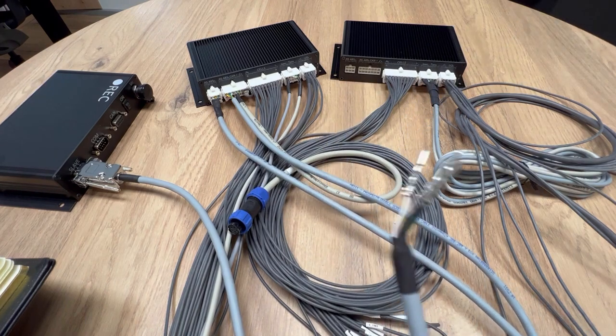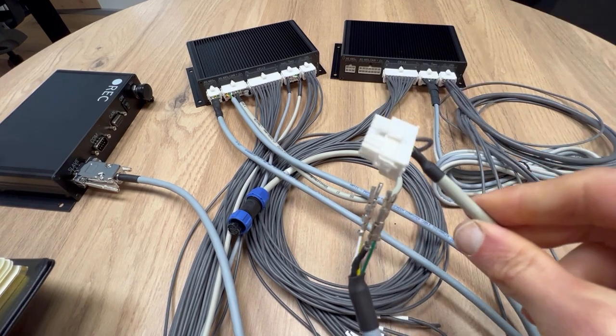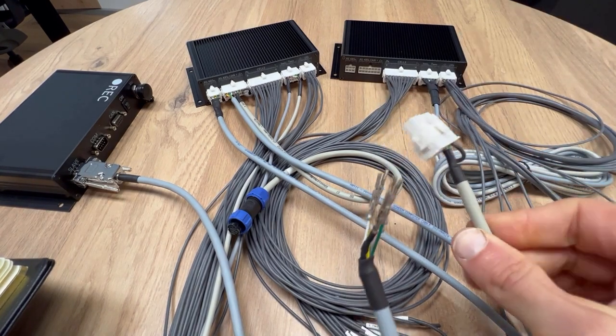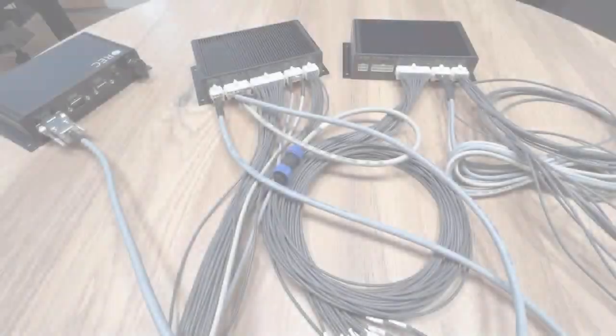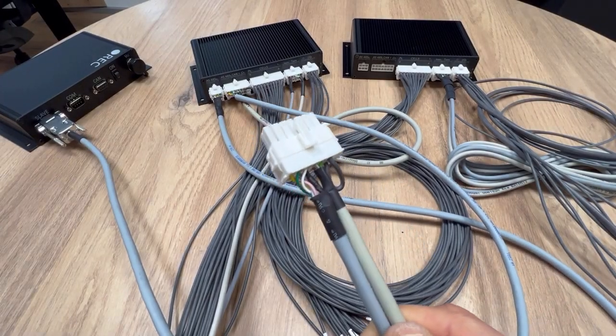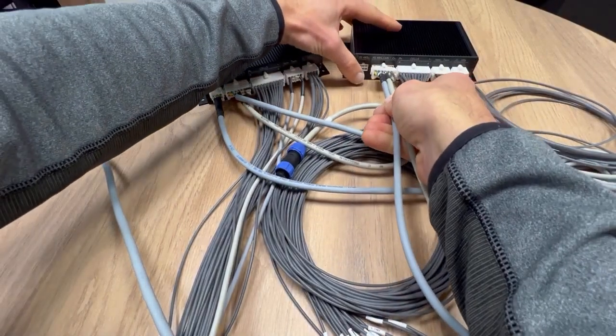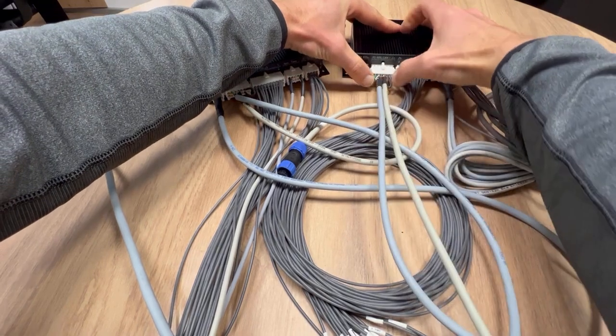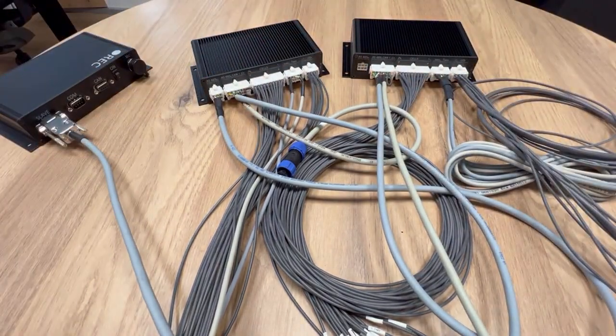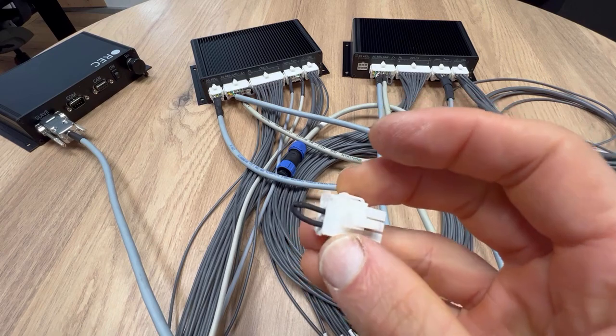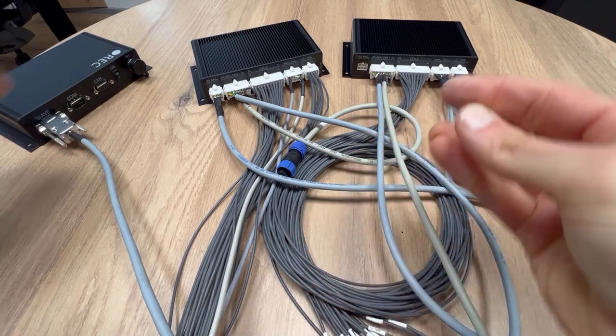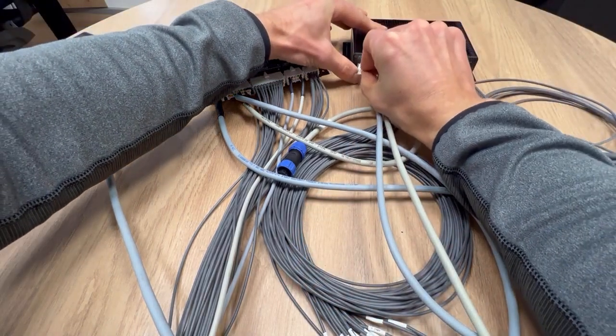Insert the loose crimps to the 14-pin input communication connector of the second slave. Insert the 14-pin input communication to the second, the last BMS slave, and terminate the bus with the 6-pin termination connector.